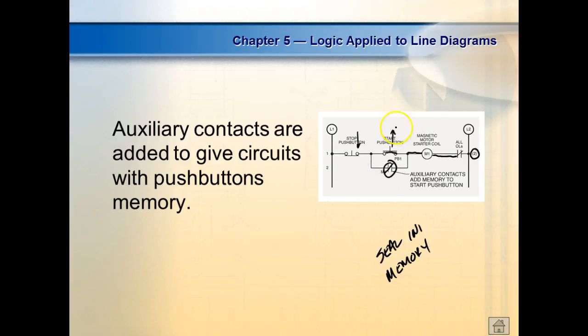This diagram is called a three-wire diagram. Anytime we have something that runs without this kind of control, we call it a two-wire diagram. As soon as I add the seal-in, we refer to it as three-wire. So this circuit has three different names: memory circuit, seal-in circuit, and three-wire circuit. All are interchangeable. But this would be the auxiliary contacts.